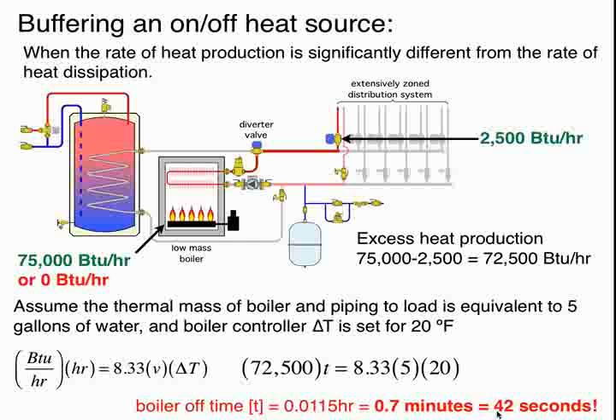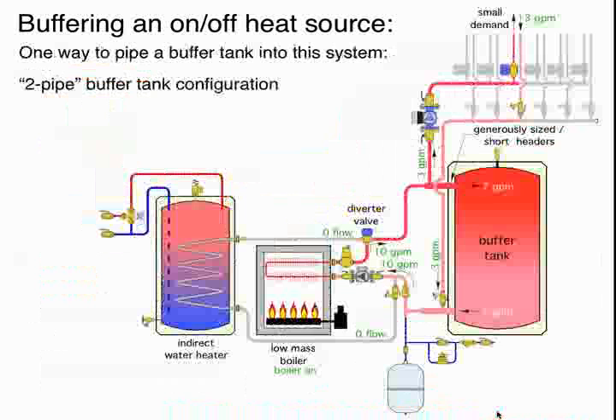There's no formal definition that I'm aware of for a short cycle, but I'd like to throw a number out for your consideration. It's 10 minutes. I think if you think about it, most boilers, heat pumps, and so forth will have a reasonable life if they can operate for a minimum on time, 10 minutes, perhaps longer under stronger, higher load conditions. But we don't want to have boiler cycling on a 42-second basis. So it shows you the problem.